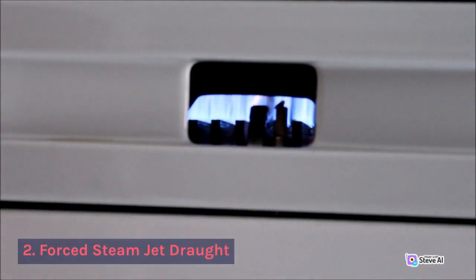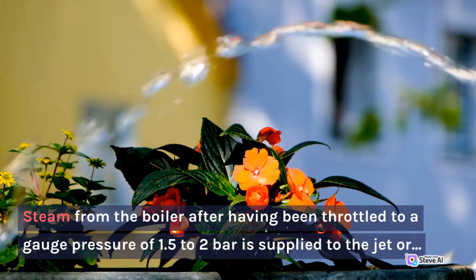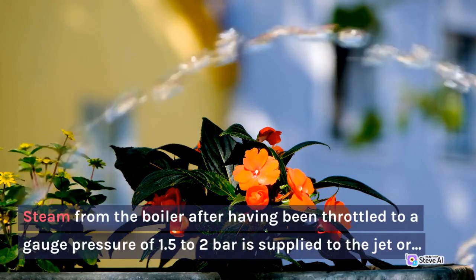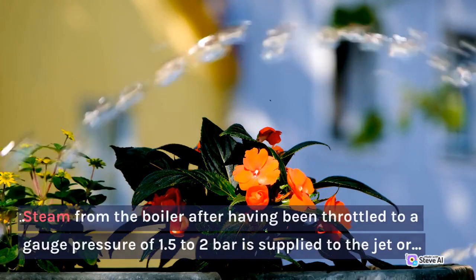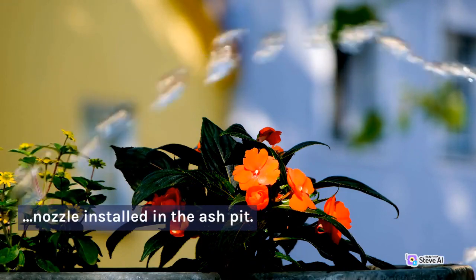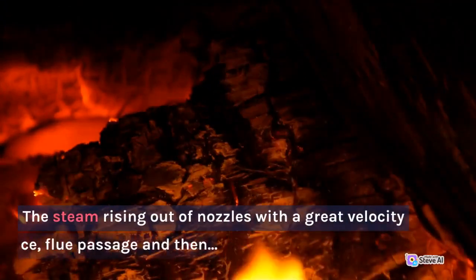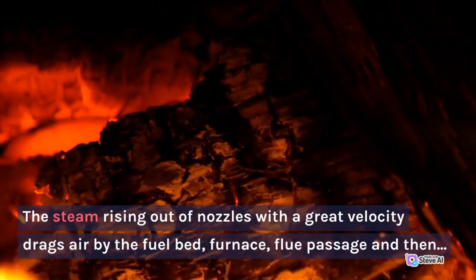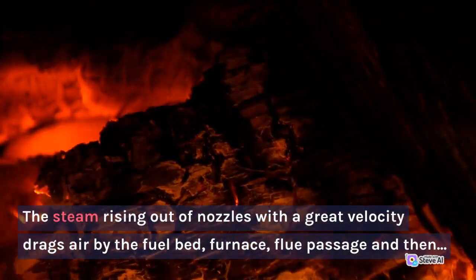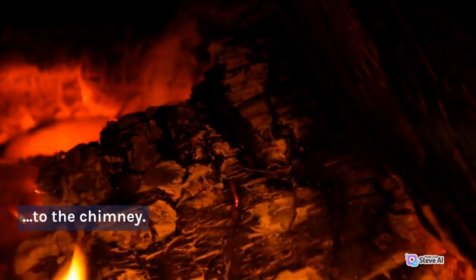2. Forced steam jet draft. Steam from the boiler, after having been throttled to a gauge pressure of 1.5 to 2 bar, is supplied to the jet or nozzle installed in the ash pit. The steam issuing out of the nozzle with a great velocity drags air through the fuel bed, furnace, flue passage and then to the chimney.